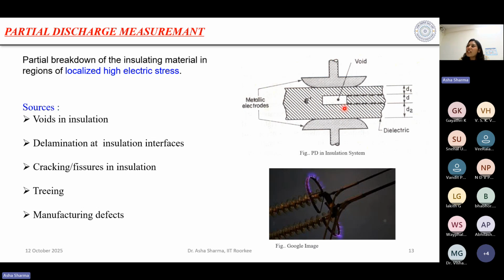How do we have the partial discharge here? Let's say again these are the insulating material. These may be manufactured by someone. So obviously the insulating material must have the same property at each and every point. But during the manufacturing, there may be some defect within this. The defect may be some foreign particles or it may be some void. A void can be an air bubble, which is a bubble of air. Air has a permittivity of 1.